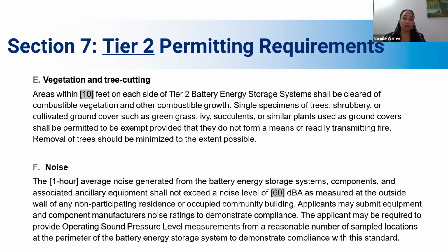Vegetation and tree cutting: 10 feet on each side of the Tier 2 BESS system should be cleared of all combustible vegetation or growth. Single specimens of trees, shrubberies, or ground cover can be used as long as it doesn't readily transmit fire. The 10 feet is per the fire code, and this needs to be maintained even after the system is built, for the entire life of the project.